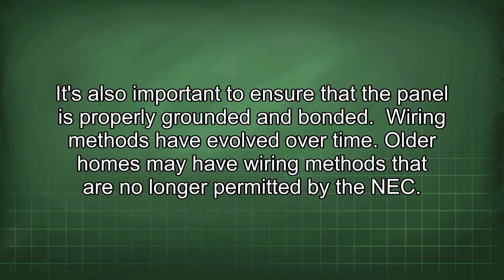Wiring methods have evolved over time. Older homes may have wiring methods that are no longer permitted by the NEC. Replacing outdated wiring with modern wiring methods, such as non-metallic sheathed cable, commonly known as Romex, can improve safety and reliability. When replacing wiring, it's essential to follow NEC guidelines for wire size, insulation type, and installation practices.